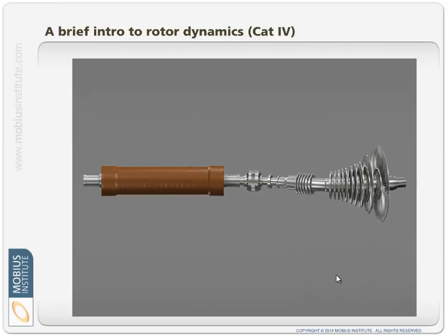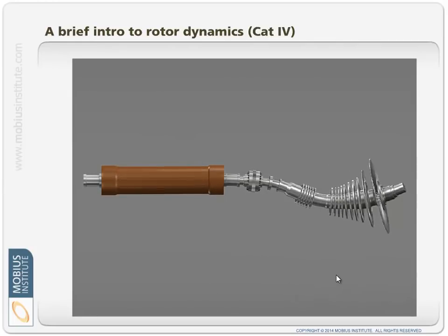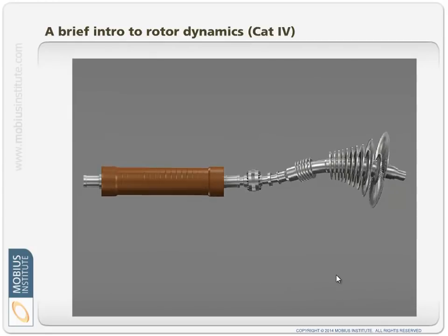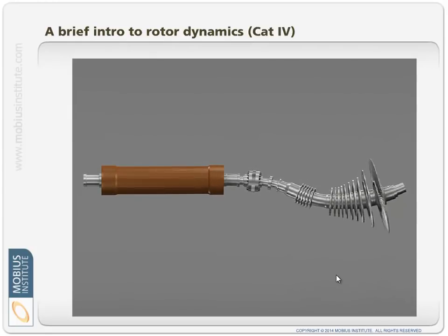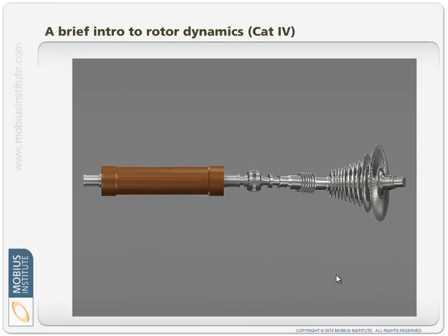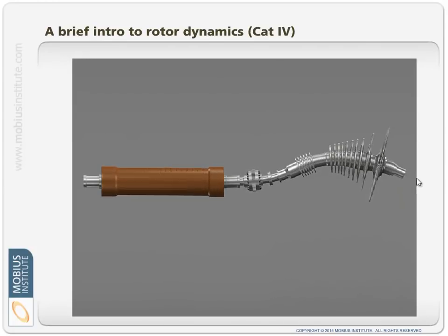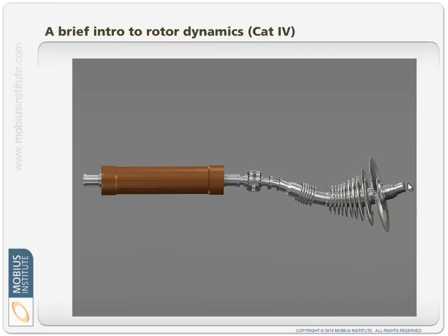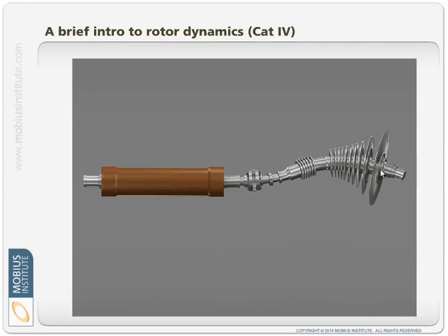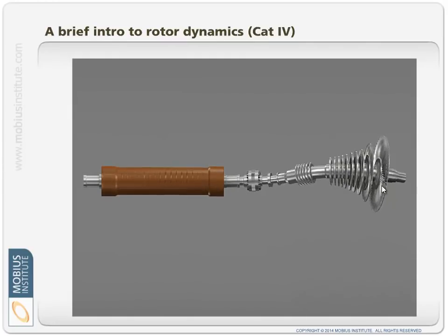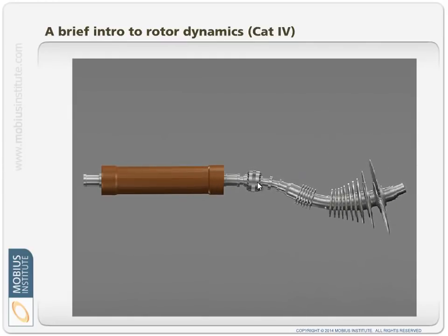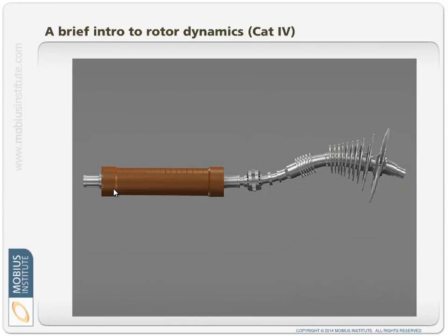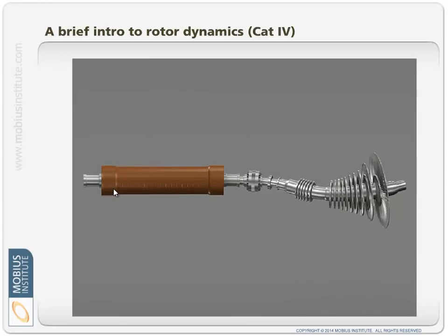Here, an important part of the rotor dynamics is we want to model the shaft and then consider modeling what it's coupled to. So in this case, we might even start with the blank casting and see how that might vibrate, and then add each of the discs to it and see how they affect things, add this great big coupling to it and turning gear and so on, and then couple it to the generator. So we can, from a modeling perspective, see how this all works.